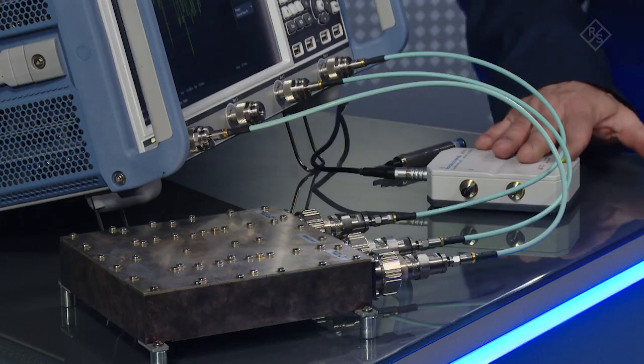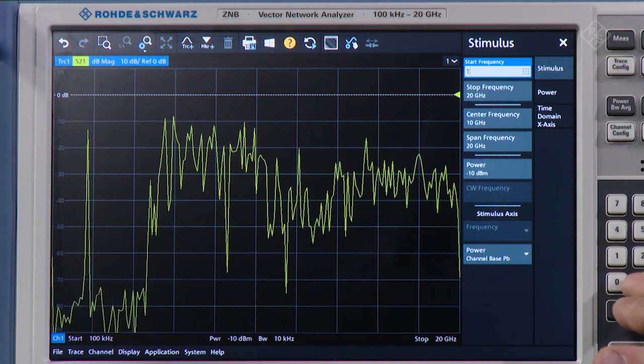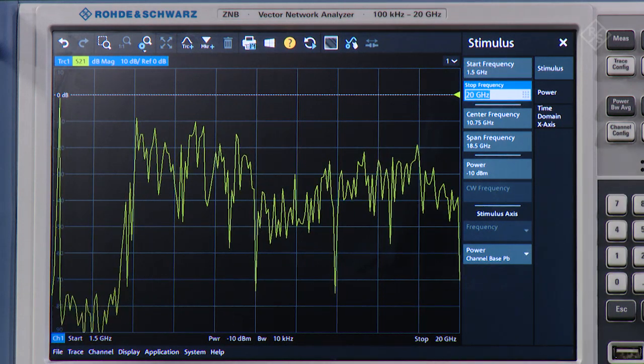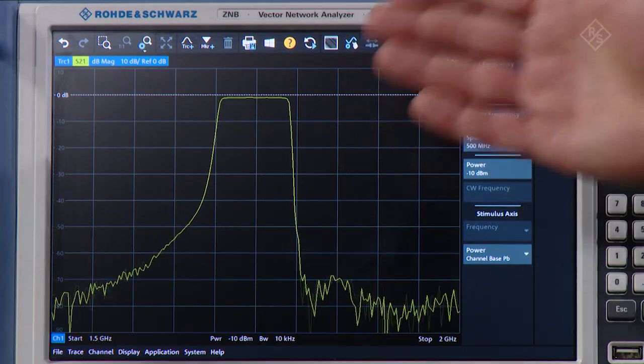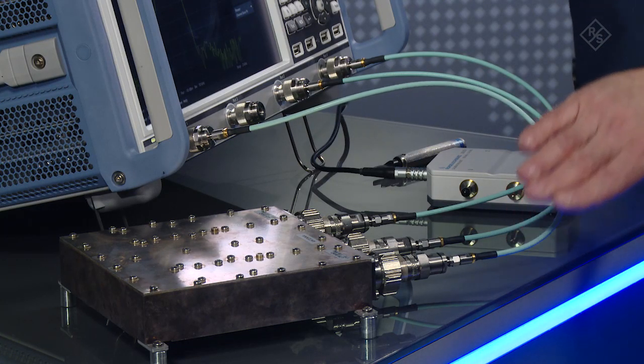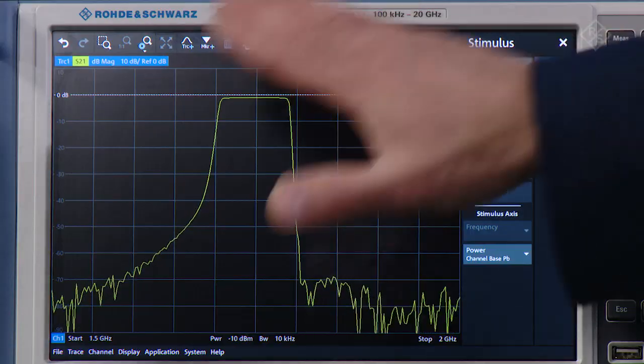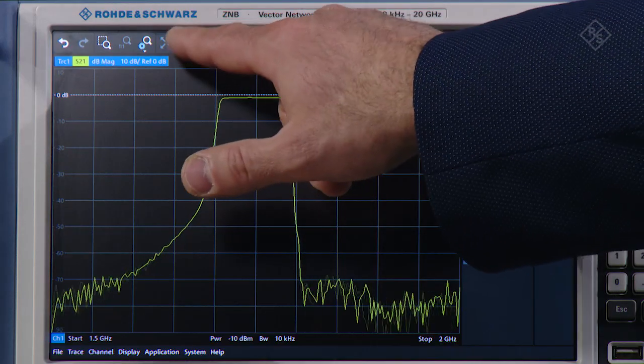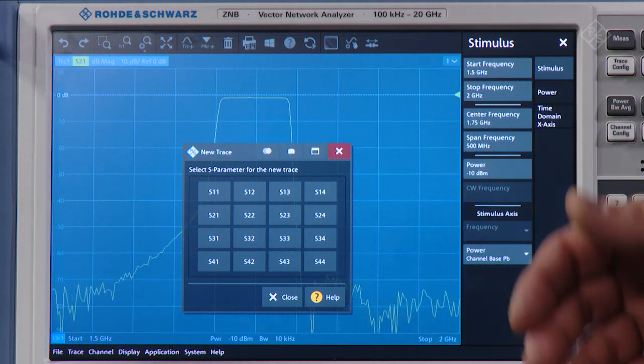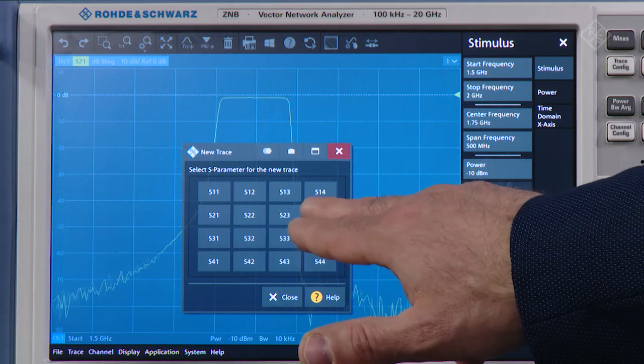I will calibrate the setup using the Rohde & Schwarz ZN-Z51 automatic calibration unit. We will begin the measurement with a preset. I will configure the measurement as follows: start frequency at 1.5 GHz, stop frequency at 2 GHz. Because the default is the S21 trace and I have connected the duplexer antenna low band to port 1, antenna to port 2, high band to port 4, we will see the low band on screen. I will simply add another trace and select S24 since the high band is connected to port 4.